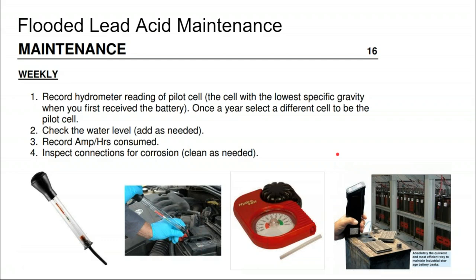The industrial flooded lead acid battery manufacturers I've talked to aren't as worried about keeping these kinds of logs in an exact fashion, if the batteries are otherwise protected and in an environmentally controlled space, like an air-conditioned, ventilated room—not an outdoor shack that rainwater can get through.